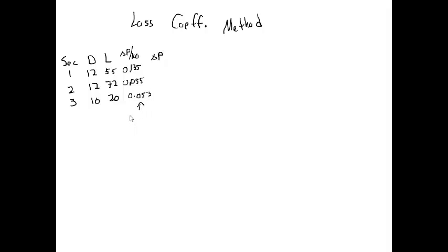I can get these from figure 1221 at specific diameters and flow rates. And then knowing my length and knowing the loss, I can find what my actual pressure loss is just for the length of pipe, not counting the fittings.